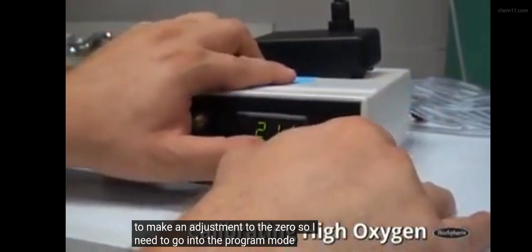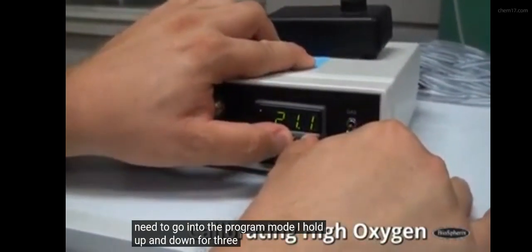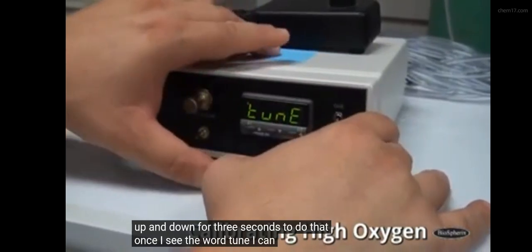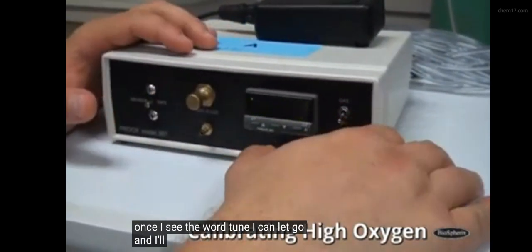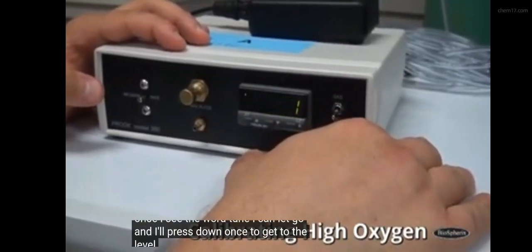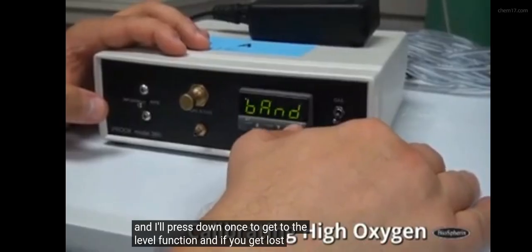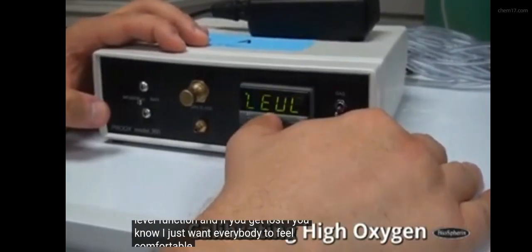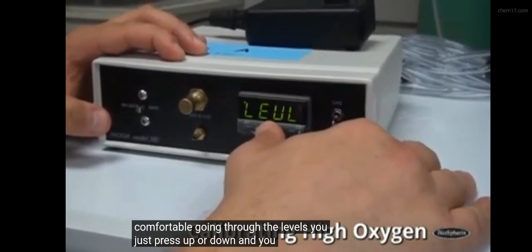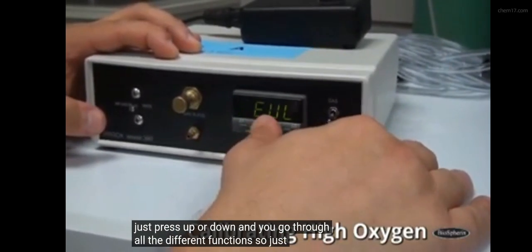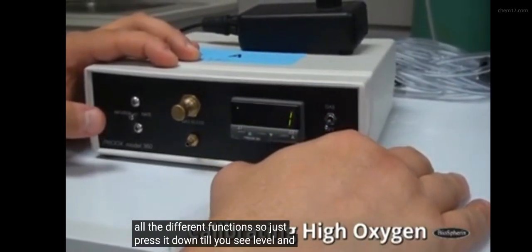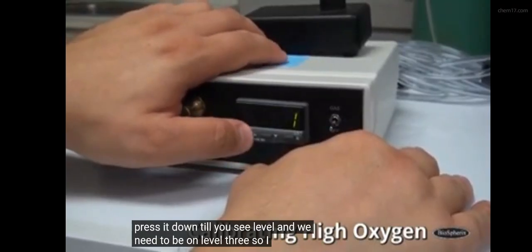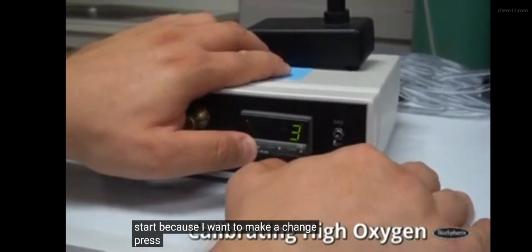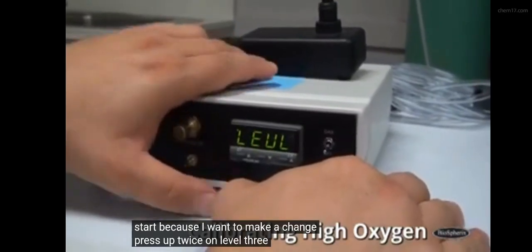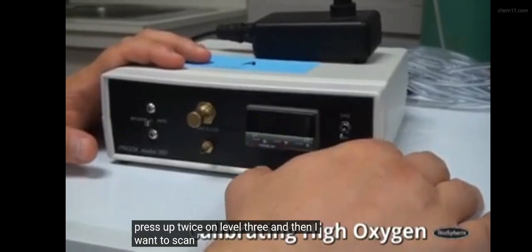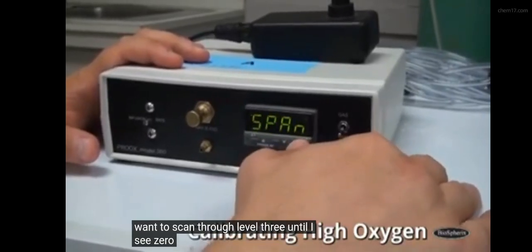So I need to go into the program mode. I hold up and down for 3 seconds to do that. Once I see the word tune, I can let go. And I'll press down once to get to the level function. If you get lost, I just want everybody to feel comfortable going through the levels. You just press up or down and you go through all the different functions. So just press down until you see level, and we need to be on level 3. So I hold the star because I want to make a change. Press up twice on level 3, and then I want to scan through level 3 until I see 0.